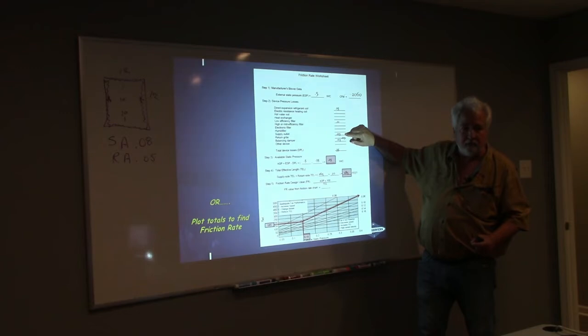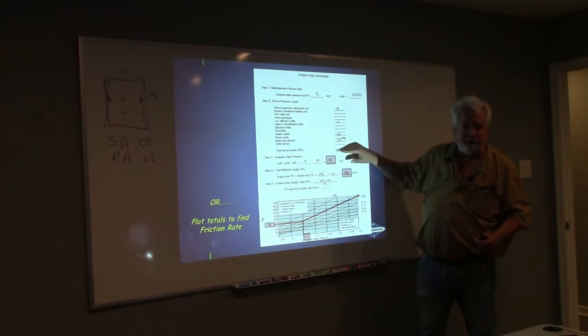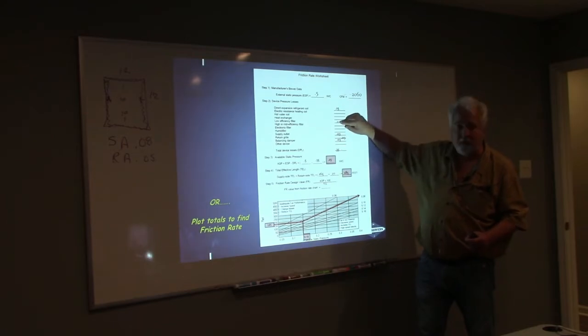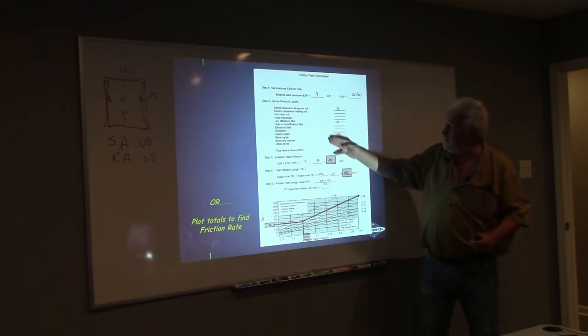This is my report. 0.03 for our supply. 0.03 for our return. 0.03 for our balancing damper. What do we have for our device losses? Add those all up. What did you end up with? Add these: 0.15, 0.36, 0.03, 0.03, and 0.03. 0.6? Look, we have 0.6 here.